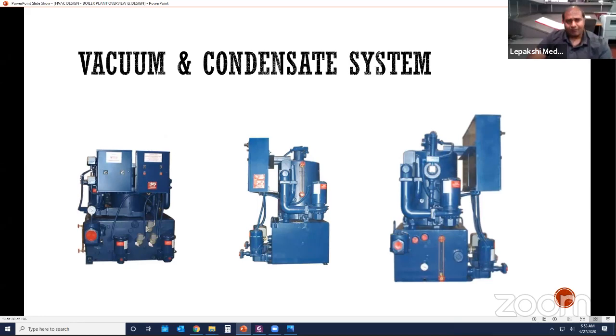Now the other concept is the vacuum and condensate pump. What is a vacuum and condensate pump? Why do you need it? So now you're generating steam, and the steam is being distributed to where it's going, right? A certain amount gets condensed when it exchanges its heat in the room. Once the steam condenses, it becomes water. So you've got to get that water back to the system. These pumps are going to suck that condensate back with the vacuum. And that's what it is.